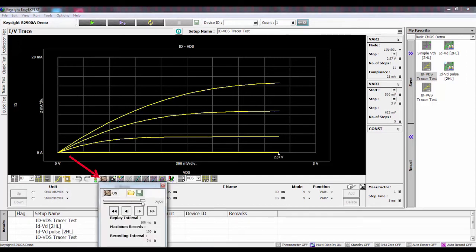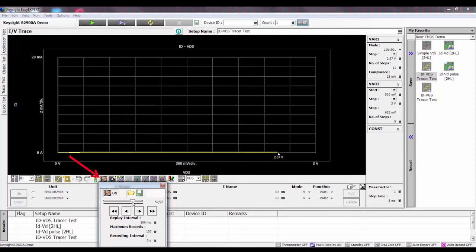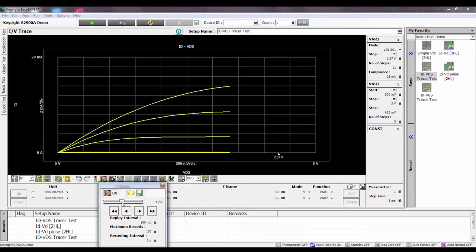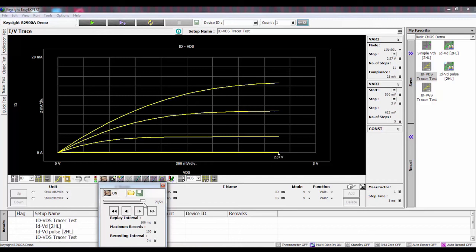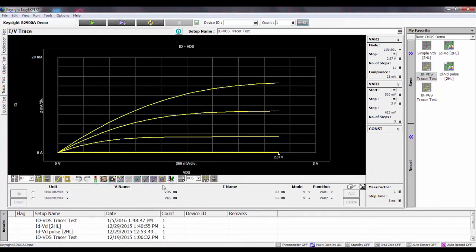I can go back and replay what I've done. For example, if I created something where I damaged the device, I could actually go back and I haven't lost the data. This makes a very nice interactive way of doing curve tracing right on the B2900 using the EasyExpert software.